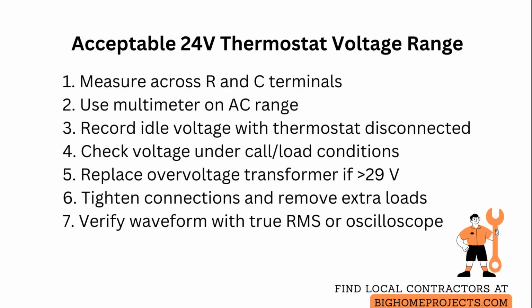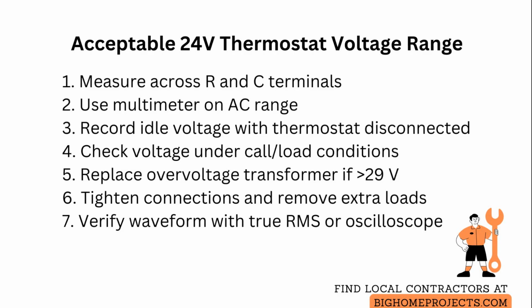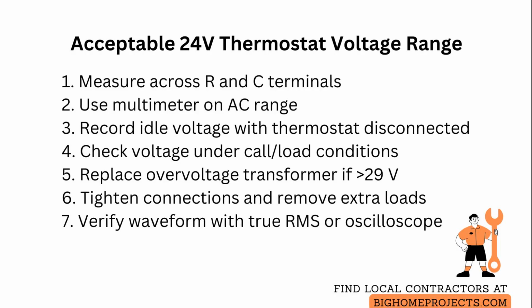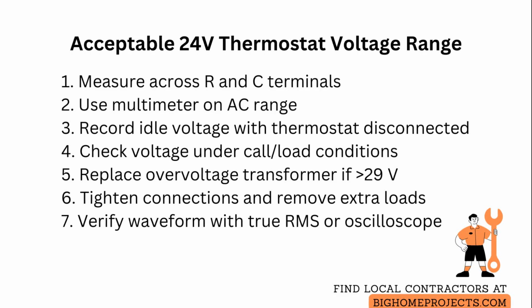If the meter shows a steady voltage above 29 volts alternating current, the transformer secondary may be over voltage, which can damage electronic thermostats and control boards. Replace the transformer with one rated for the correct nominal secondary voltage.